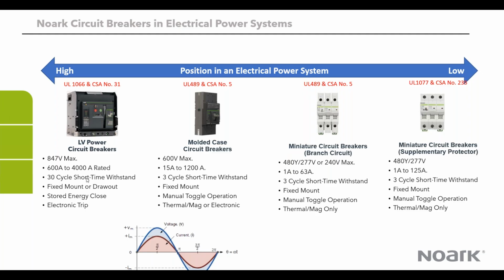This is important because when you start designing a system, you don't want your main breaker, the one situated in the main switchboard, to react first to any fault. You need this withstand rating so you can delay the reaction of the main circuit breaker and allow all the other breakers downstream in the feeder circuit or in the branch circuit to react first to the fault. So that's the importance of the withstand rating. And if you look at the molded case breaker here, it's a 3-cycle short time withstand. So it does not have the ability to withstand the fault for a longer time. Essentially, depending on the design of your system, you don't want to use this at the main incoming of your system because it has a shorter short time withstand.